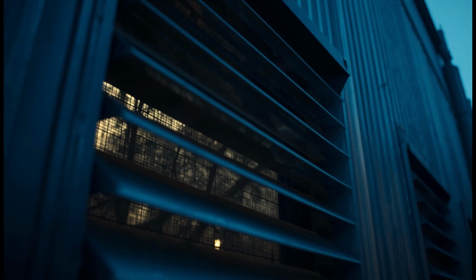Just beyond the louvers, the path narrows into a short section of ductwork, and here the first true decision-making component of the journey waits quietly in the dark. This is the outside air damper, a bank of wide metal blades mounted on a shared axle, stretching the full width of the duct. At this hour, the blades sit at a modest angle, neither fully open nor fully closed, allowing a measured trickle of outdoor air to pass through, while the building maintains only the minimum ventilation it requires during these unoccupied hours.